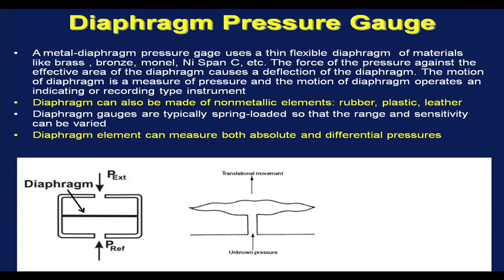Diaphragm gauges are typically spring loaded, so that the range and sensitivity can be varied. For non-metallic diaphragms, they are usually spring loaded because non-metals do not have good elastic property like metals such as brass, bronze, monel, Ni-Span-C, etc. Diaphragm elements can also be used for measurement of differential pressure as well as absolute pressure.